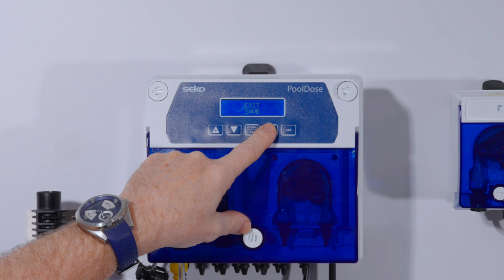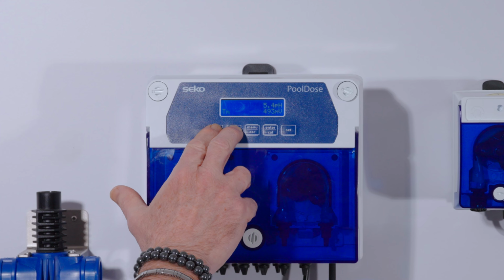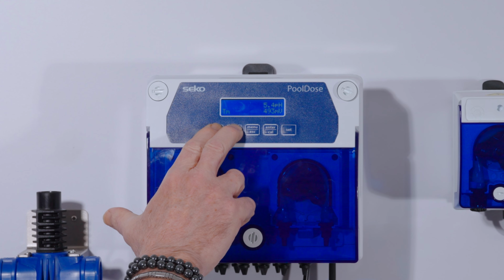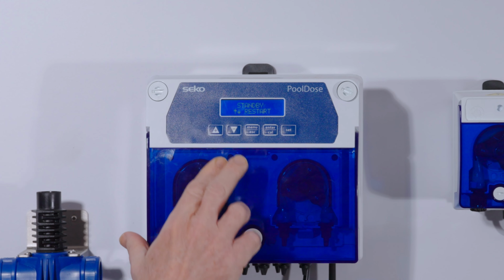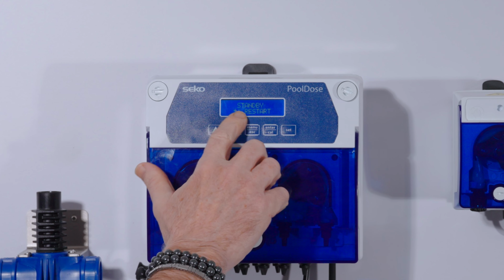To prime the system on first start up, we press and hold the plus and minus button until we see standby and restart. If we then use the down button, we can prime the acid pump, and if we press the menu button, we can prime the chlorine pump. To resume normal operation, we just press the up and down buttons again.